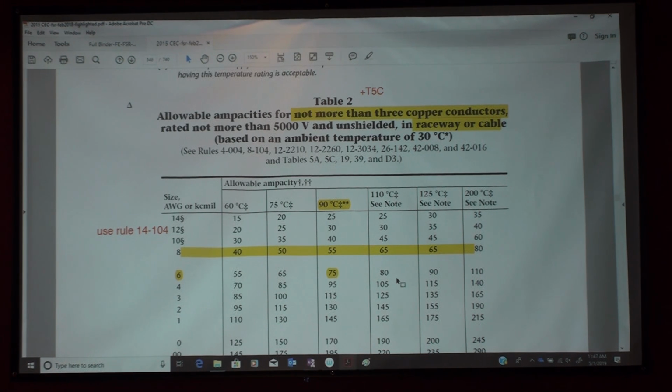But the moment conductors are in a raceway, because they're all tied together in the same path, they cannot carry the same ampacity as the charts. You have to derate that. Good? Same story. Just to confirm, a raceway or conduit doesn't include like a rubber insulator, correct? Rubber insulator for the wire, you mean? If they are in any kind of path, together with a bunch of wires, you gotta derate them. No matter what kind of path. Any raceway is actually a path. It could be a cable tray or any kind of conduit, any kind of cable where a bunch of conductors are put together, you gotta derate them.